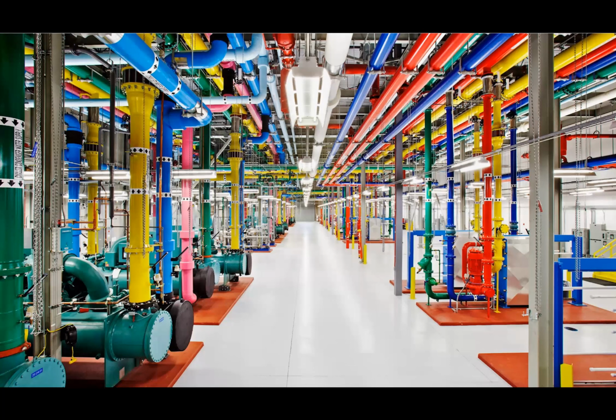In this picture alone you see a lot of chillers on the left-hand side, the big greenish-looking cylinders. These chillers convert hot water into cold processed water that goes back to the server floor. You've got condenser water pumps and processed water pumps serving the system, some heat exchangers, and a bunch of valves. A lot of moving liquids.